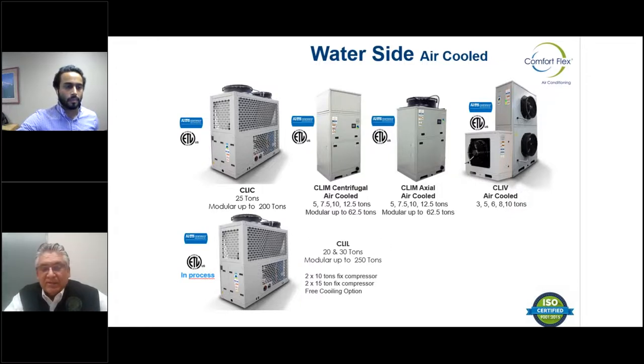If you look at the air cooled product, they have both centrifugal as well as axial fans. If you look at the centrifugal one right here, what's really unique about it is if you had a high rise or semi high rise and you wanted to add chilled water to the application, and you don't have any, and maybe you need room on the roof for an air cooled chiller, you can actually position this on each level depending on the tonnage range. It has a centrifugal blower wheel for the condenser air, which can be ducted into the chiller and then straight back out the chiller. It can handle up to about 1.5 inches static, so it's a great unique application in that respect. They have a lot of those installations in Mexico. We're the first, and please don't take that the wrong way, but we're the first rep for them in North America. They're expanding beyond Mexico, and they wanted to find somebody they could partner with. We felt this was a good opportunity for us, and also a great product to provide solutions.